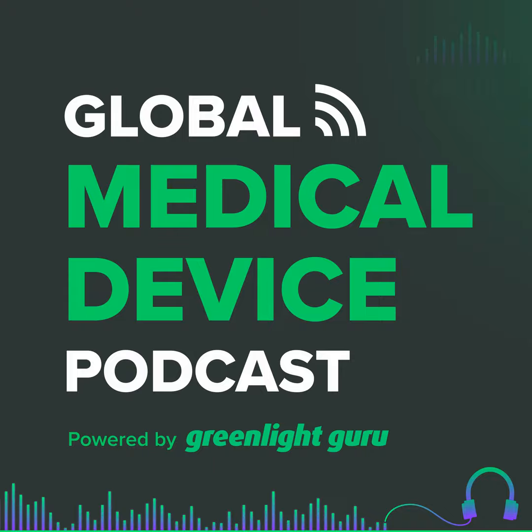Great question. So the easy part of the answer is, and I alluded to this earlier, if you're working on a brand spanking new device, a device that is not on the market here in the United States. It might be on the market in other places in the world, but not here in the United States, and you need to do a clinical trial. Absolutely, you're going to need IRB approval, as we talked about earlier, and you're going to need IRB approval at each and every one of those institutions that you're going to be doing your clinical trial at. Whether or not you need FDA approval to do the clinical trial, that's going to be contingent on whether it's significant risk or non-significant risk, as we just talked about a moment ago. That's the easy part. That's the black and white part.